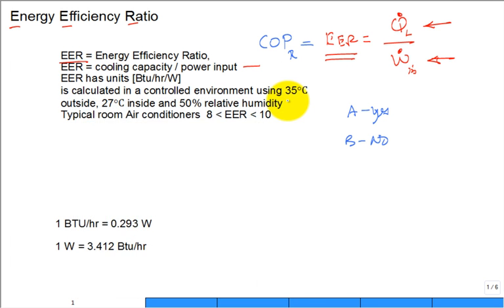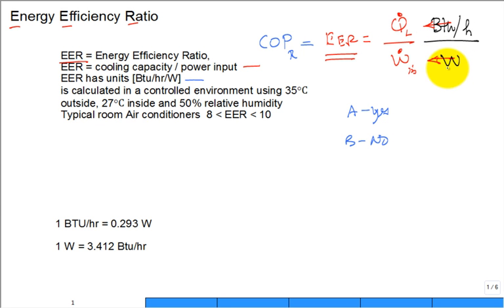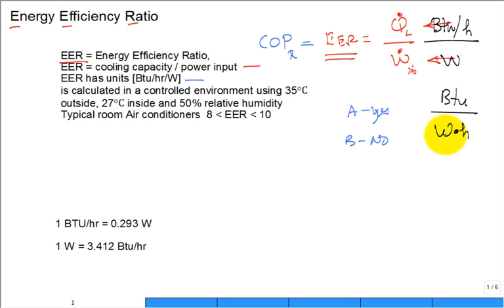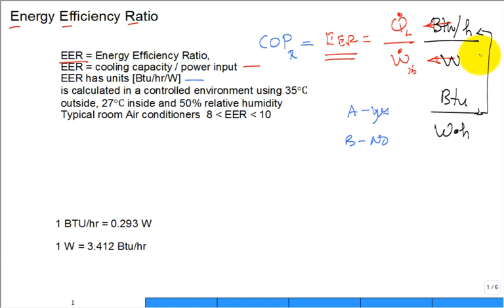They really are the same, but what's different is that EER has specified units. The Q̇ is in BTU per hour — it's a rate of cooling — divided by watts coming in. Someone might say it's BTU of cooling per watt-hour of electricity used, like a kilowatt-hour — that's how they sell electricity, about 10 cents a kilowatt-hour. Either way it's the same, so they're essentially dimensionless but with particular units associated with the EER.